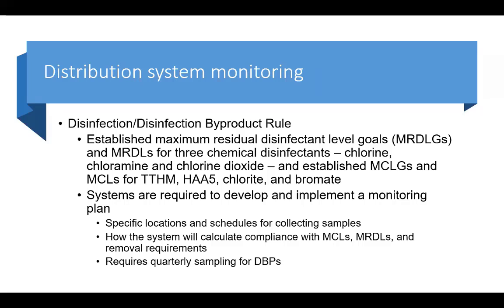These have been established for chlorine, chloramine, and chlorine dioxide. For instance, for chlorine, it's 4 milligrams per liter as the maximum residual disinfectant level.